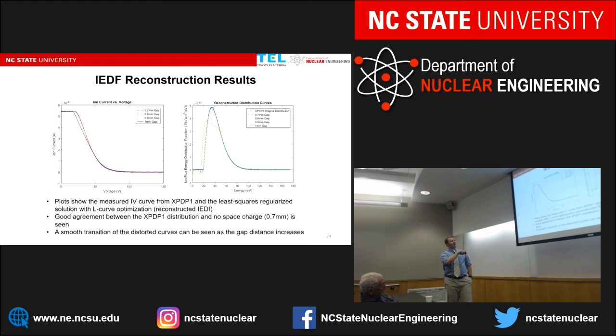There are a couple of interesting things to note. One, we still have our saturation current, which is good. But then there's a point where all of a sudden the curves match up again and follow the same trend, which is interesting because it means space charge is really only affecting the low energy ions. So if you're taking a measurement and don't care about low energy ions, space charge doesn't matter. However, if you want a full spectrum analysis, or you have conditions that will give you low energy ions, space charge could definitely be an issue you have to take into consideration.